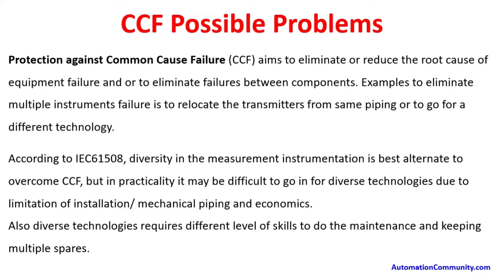CCF possible problems. Protection against common cause failure aims to eliminate or reduce the root cause of equipment failure, and to eliminate failures between components. Examples to eliminate multiple instrument failure include relocating transmitters from the same piping or going for a different technology in pressure measurement, flow measurement, or differential pressure measurement.